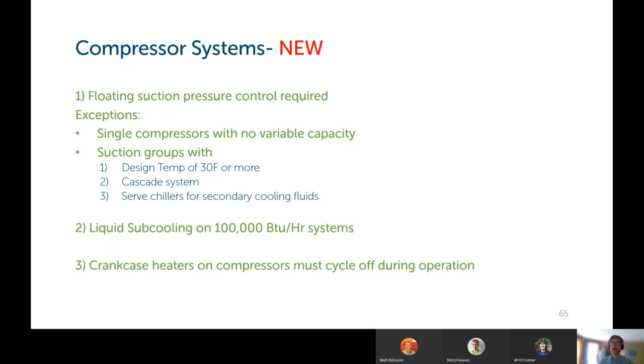A new system on refrigeration that's been added is on compressor systems. It states that floating suction pressure control is required. Exceptions to that are single compressors that do not have variable capacity, or certain suction groups with these three criteria: design temp 30 degrees or more, cascade systems, or serve chillers for secondary cooling. And to be clear also on this, suction pressure control is different from floating head pressure, so that doesn't negate our ability to claim savings and to offer incentives for floating head pressure control going forward. This is a different type of control. Okay, great. The language is a bit confusing. Yeah, I had to look into it and ask some questions. I wasn't sure either. Great.